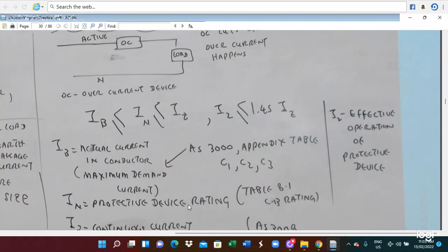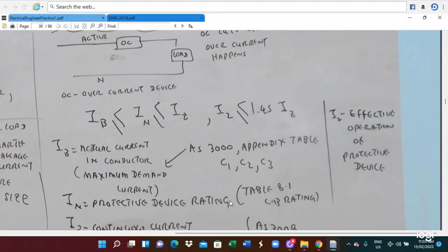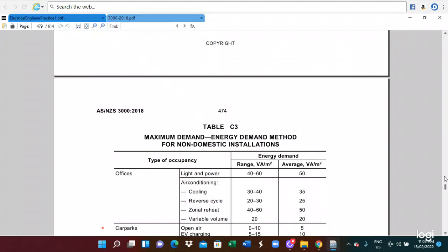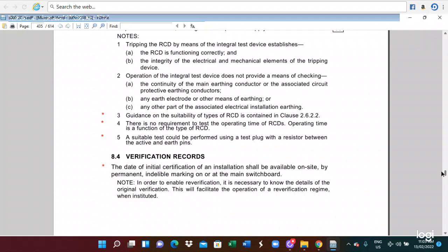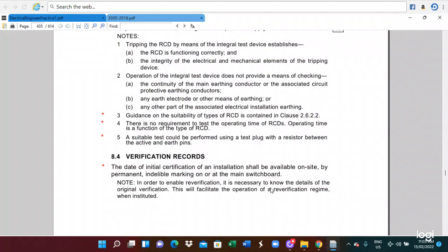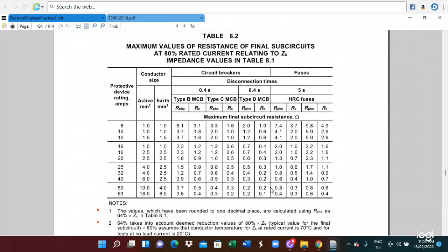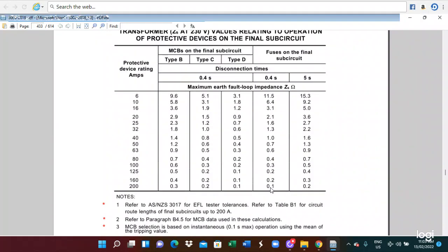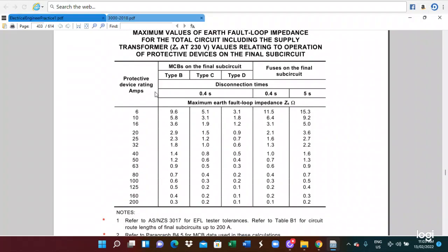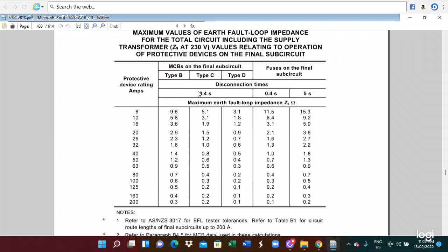IN is the protective device rating. Protective device rating means we have to use an appropriate circuit breaker rating or fuse rating. So how do we select the protective device rating? We refer to the AS3000 rule and table 8.1. In table 8.1 we have the type B circuit breaker, type C circuit breaker, type D circuit breaker. The operation time is 0.4 seconds.